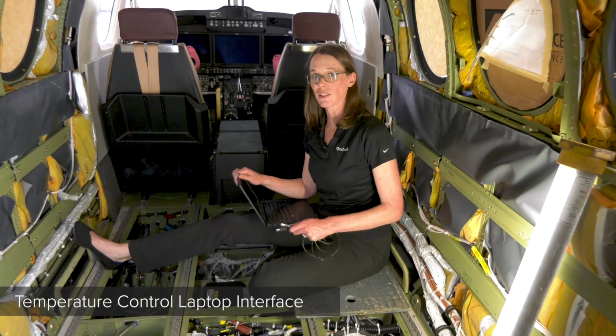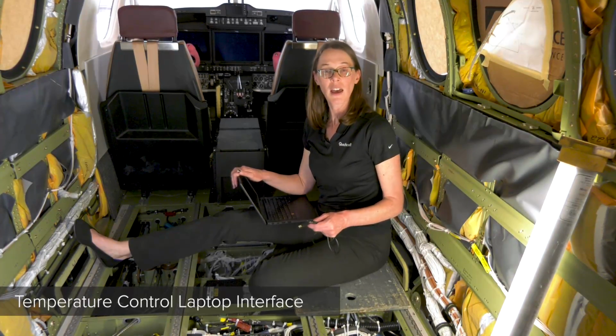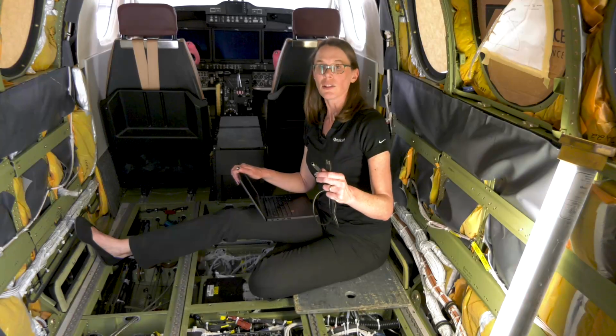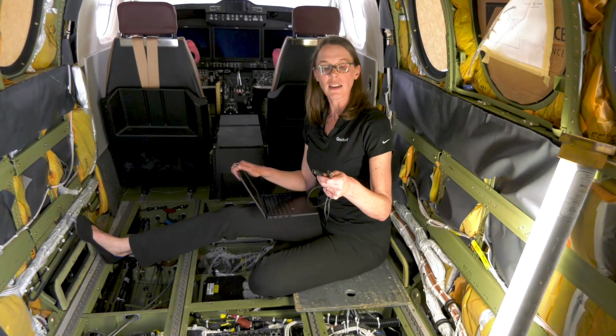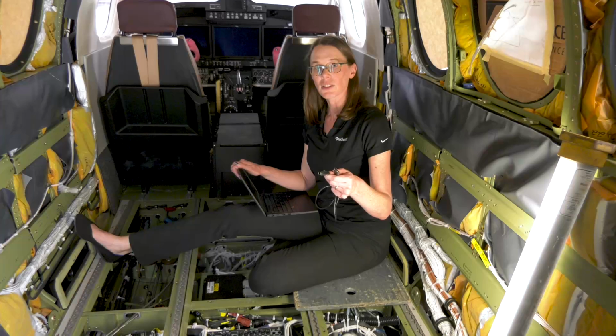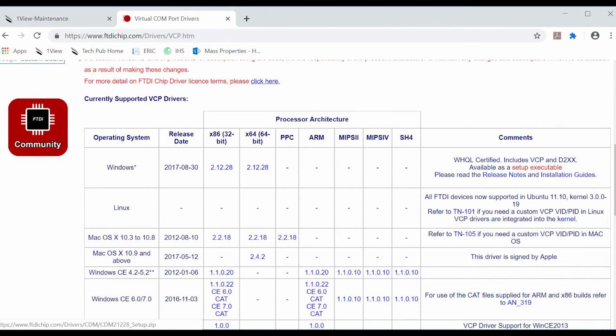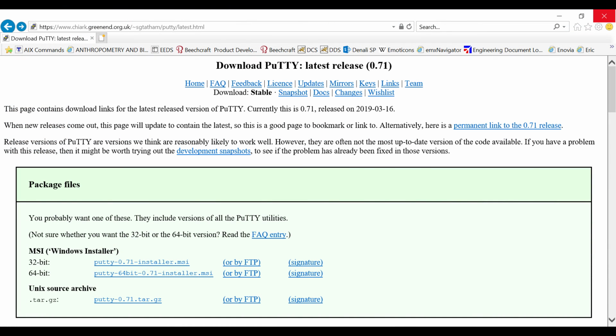You need 2 things to connect to the controller: a laptop with Windows 7 or better, and a USB cable. The USB cable is commonly found on computer printers. It needs a USB-A and a USB Type-B connector. Your computer needs a virtual COM port driver available from ftdichip.com. From the drivers page, click on Virtual COM port or VCP drivers and choose the latest Windows setup executable. Unzip this download file to your computer and either run the installer, or you can have it ready when your computer connects to the controller and prompts you for drivers. You'll also need PuTTY, a serial communications program. You can download either the 32-bit or 64-bit Windows installer from putty.org.